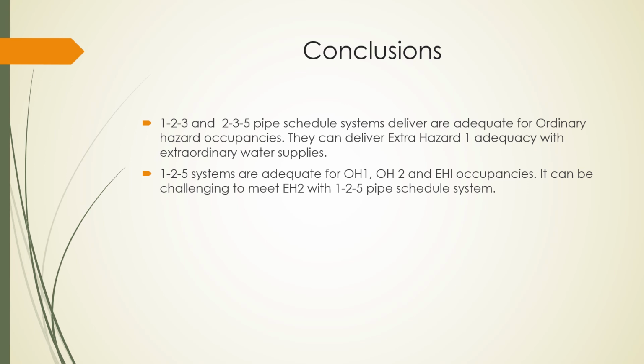But that doesn't mean that what we've just gone through in these past exercises doesn't have some relevancy. What you're doing is being able to look at a system, make a rough judgment as to where you stand and what needs to be done, and prioritize the work. So you go into a facility that's got a 235 pipe schedule system. They're doing some kind of solvent cleaning operation. It's got 80 psi at the riser.